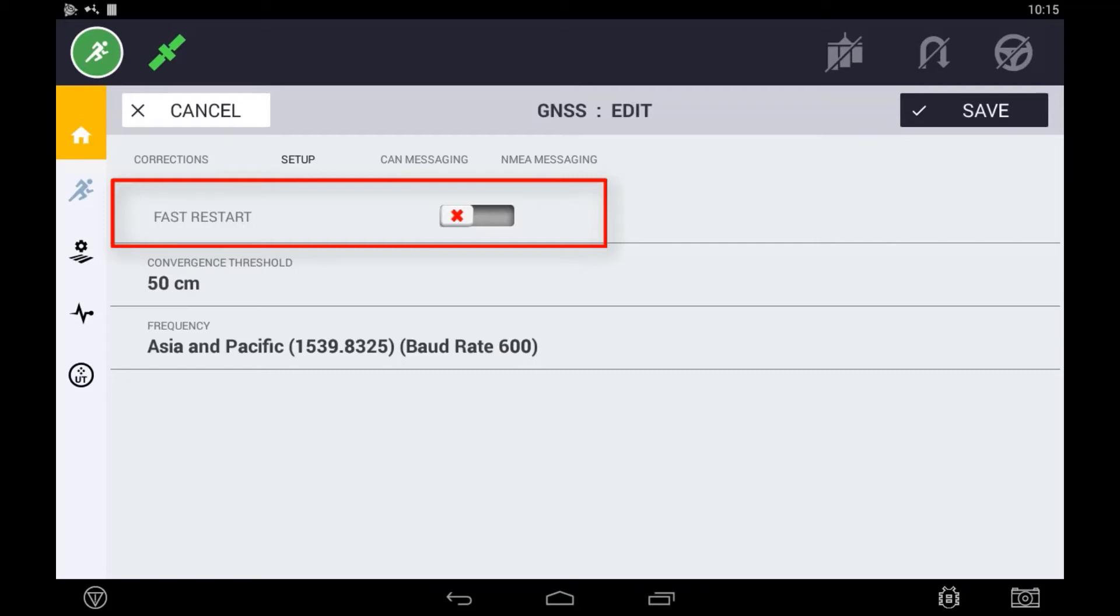In order for Fast Restart to work, the system must have been converged to a minimum of 4cm horizontal error before it is shut down. Secondly, when the unit repowers, it must remain stationary until a notification is seen indicating that the unit can now be moved.